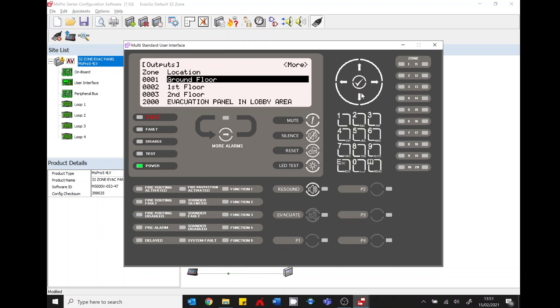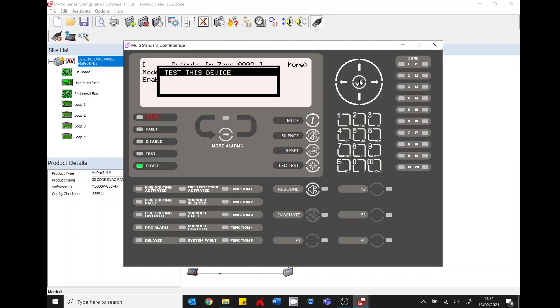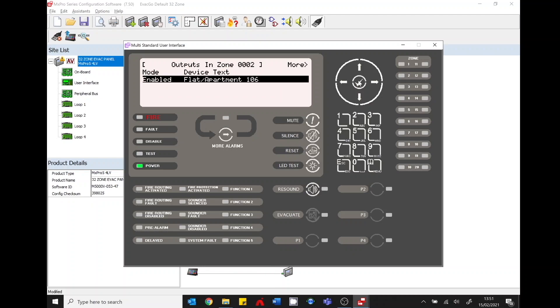So scroll down onto your next zone or your next floor, first floor. Scroll to the right hand side and you can see I've got flat apartment 106. Press the tick button. Test the device. You can hear the sounder.